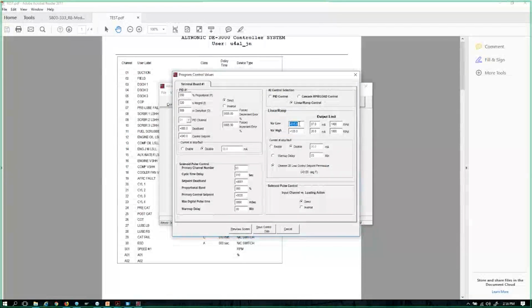And if we're basing it on suction pressure, which we are, again, and that's one thing I left out when I was explaining this screen, this section looks at channel 1 by default, so suction pressure. But let's say somebody wanted to control their speed based on discharge pressure. Well, one, with the statement I just made about it being defaulted to look at channel 1, we would have to reconfigure our channels. We would have to move discharge pressure to channel 1.